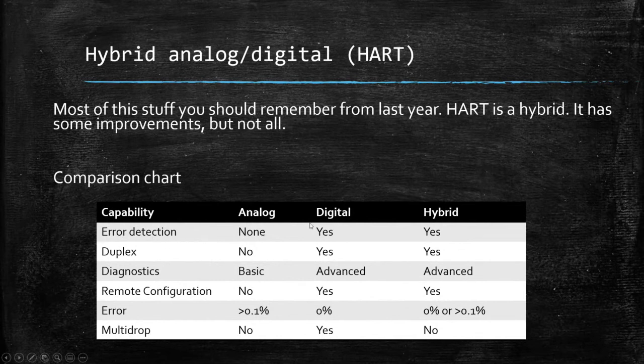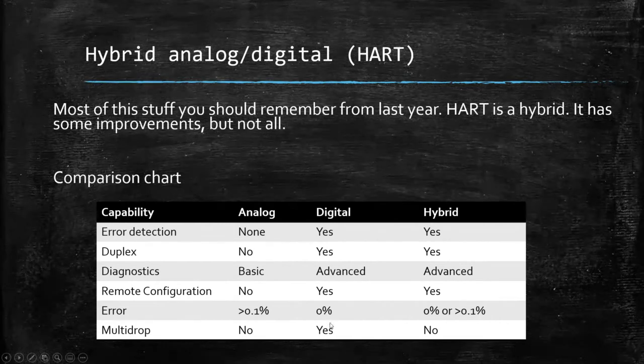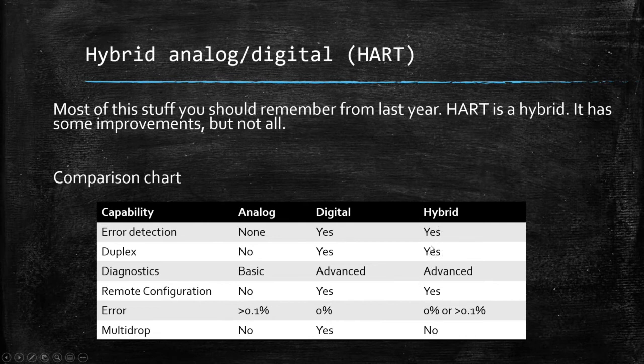Here's a comparison chart for hybrid, digital, and analog devices. Does analog have error detection? No. Digital? Yes. Hybrid? Yes, some. Analog has no duplex, basic diagnostics, no remote configuration, about 0.1% error, and no multi-drop. Digital gets the full meal deal — all the features checked, leather interior, club seats. Hybrid gets some of the features, not all, but you'll see an improvement over analog in most cases.